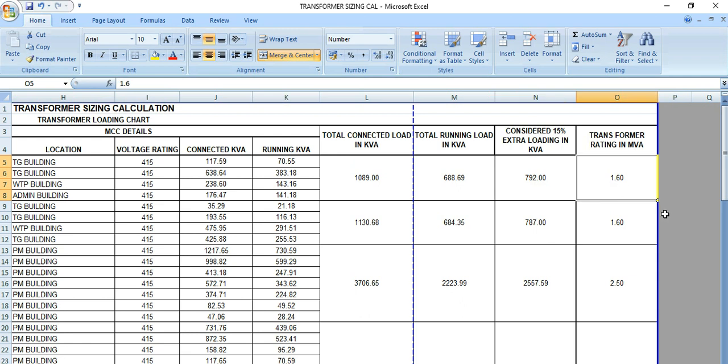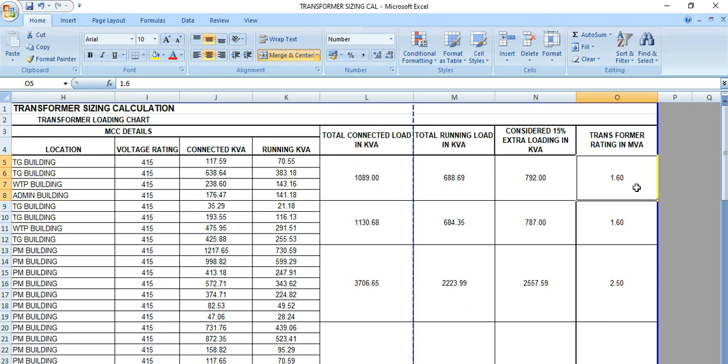After imposing this margin, then also we are considering here 1.6 MVA. But still, this 1 MVA transformer, that means thousand kVA transformer, is enough for this. But just to stay at a higher side, stay safe, we are considering here 1.6 MVA transformer, though it is on the higher side.